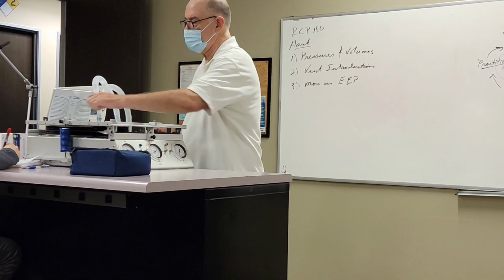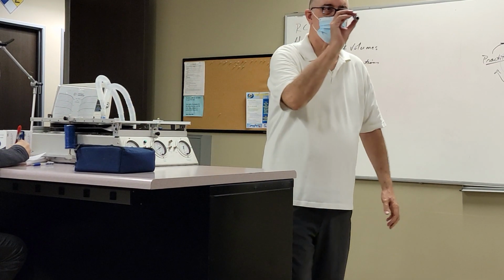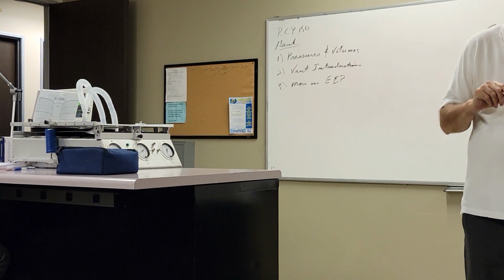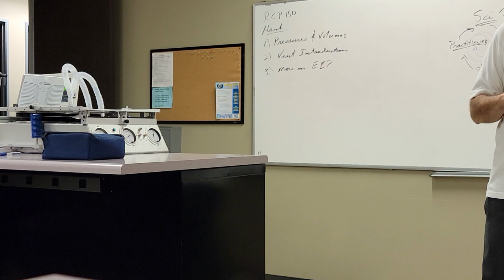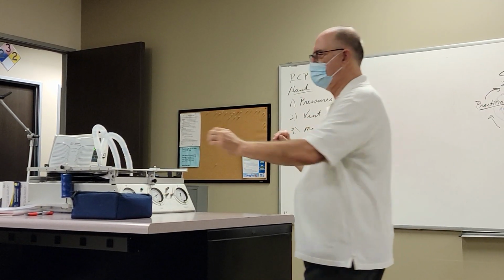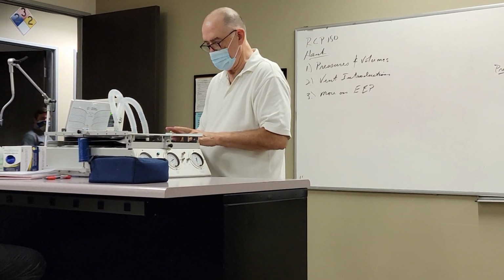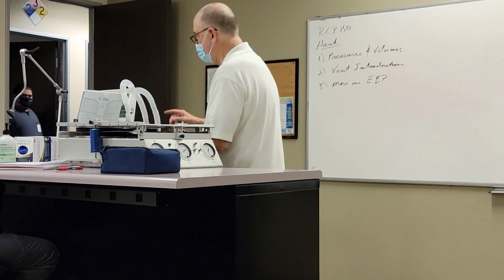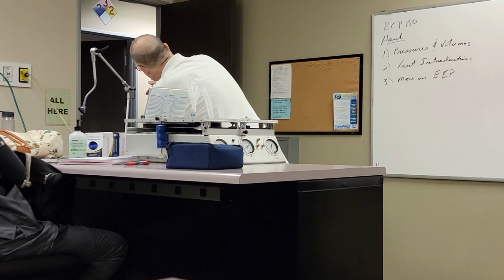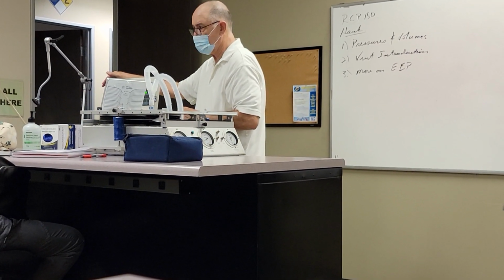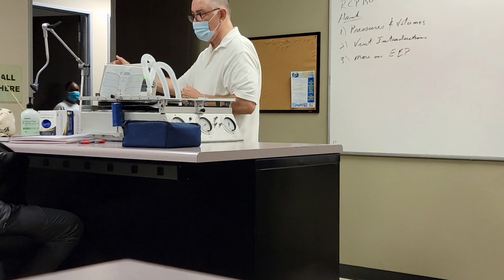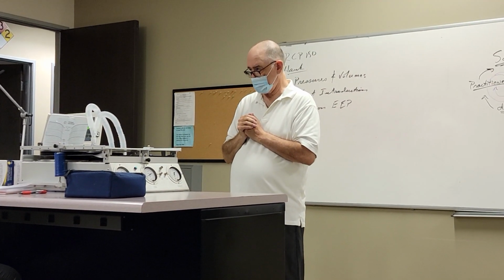So we have a resistance. The size of the orifice of this, see a little hole? Yeah. This is restrictive. Yeah. So there's a lot of resistance through this. That one, not so much, okay? And right now, I have set the compliance to a normal level. So compliance and resistance are normal. We will see that our peak airway pressure is 11 centimeters of water pressure for a tidal volume of 400 ml. Okay? This is a normal patient coming out of OR, okay, fully relaxed and all, okay? And sitting in a semi-Fowler position, okay?